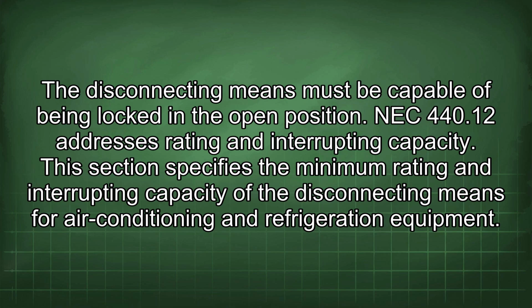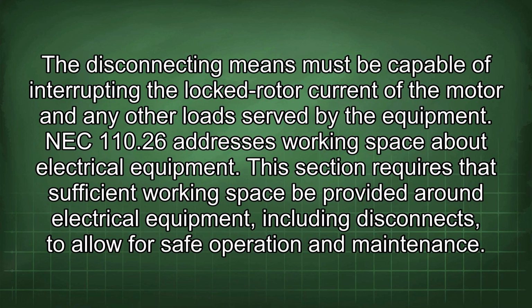NEC 440.12 addresses rating and interrupting capacity. This section specifies the minimum rating and interrupting capacity of the disconnecting means for air conditioning and refrigeration equipment. The disconnecting means must be capable of interrupting the locked rotor current of the motor and any other loads served by the equipment.